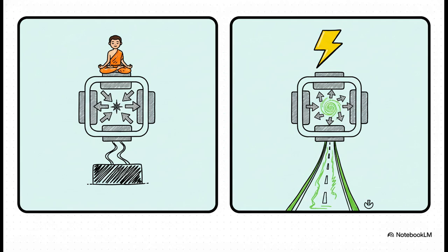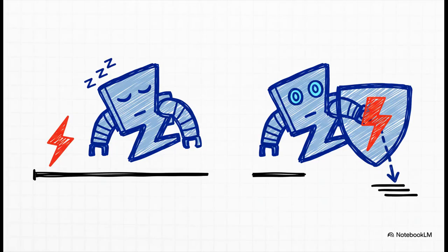But the moment a ground fault happens, that beautiful balance is completely shattered. The system is suddenly unbalanced. All at once, those magnetic forces no longer cancel out, and the transformer instantly switches from being a high-resistance roadblock to a low-resistance superhighway, giving that dangerous fault current an immediate, safe path straight to ground. That's the genius of it, a passive guardian. It does absolutely nothing 99.9% of the time, but it's always ready to spring into action in the millisecond a fault happens, protecting the entire grid from a potentially catastrophic failure.